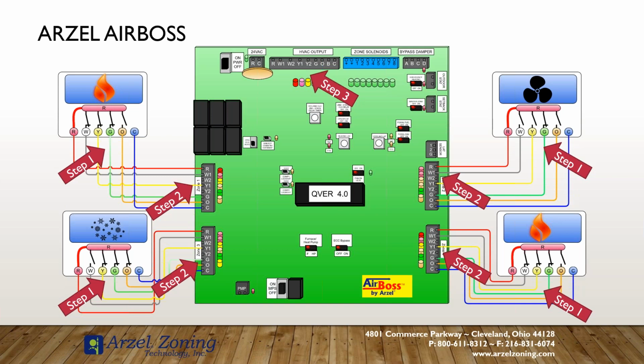WYG closed is a call for heat pump with auxiliary heat. So this would actually be an all electric application. You have your heat pump, your thermostats are calling for the compressor, and then you have one stage of electric backup heat, W, and your thermostat determines it needed to call for the auxiliary heat.